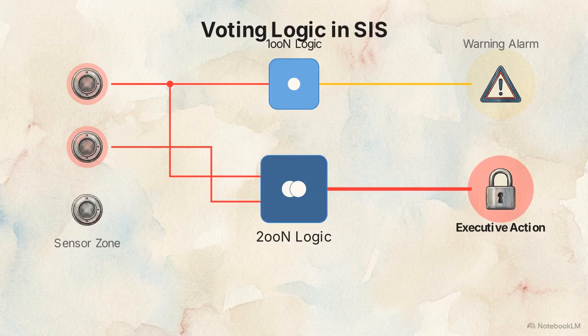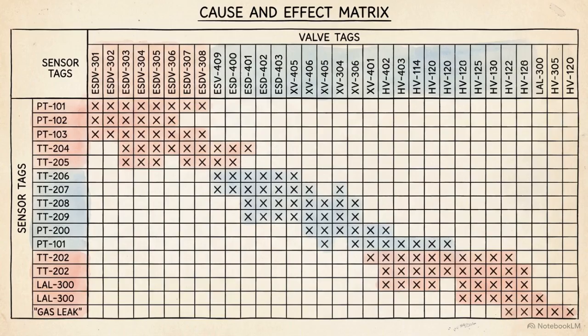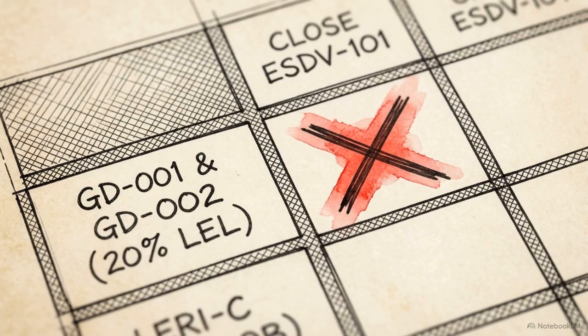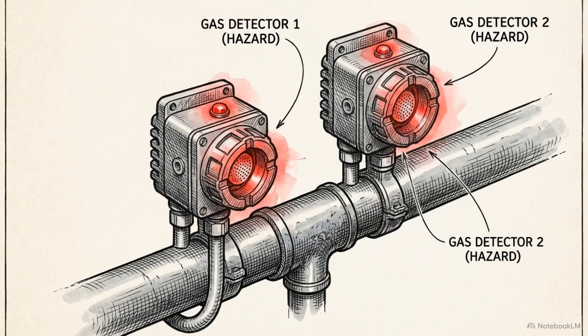This logic is governed by the cause and effect matrix. This master engineering document defines the exact mechanical responses, like valve closures and deluge activations, that must occur when specific voting thresholds are met. Voting logic ensures that a facility only shuts down when a physical hazard is mathematically verified by multiple instruments.